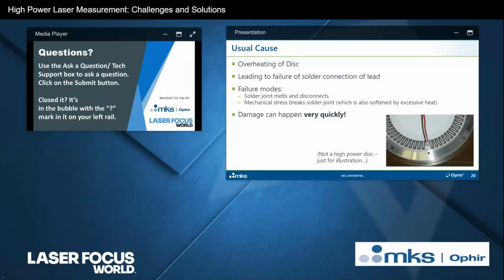Failure mode 1, the solder joint melting and disconnecting, is going to bring about what I called instant sensor death, disconnecting and remaining disconnected. Failure mode 2 can sometimes lead to intermittent failure. Under laser exposure, the disk heats up and the solder joint disconnects, but then it reconnects when the disk cools back down, and so on. Or it could just become unstable and maybe disconnect, maybe reconnect, maybe partially disconnect, and then you get that weird erratic behavior that we saw in that video clip that actually was sent by a customer who was experiencing that problem.